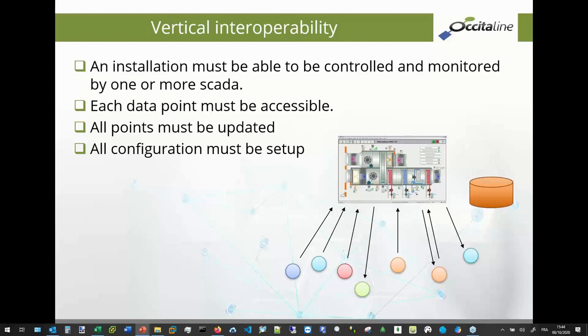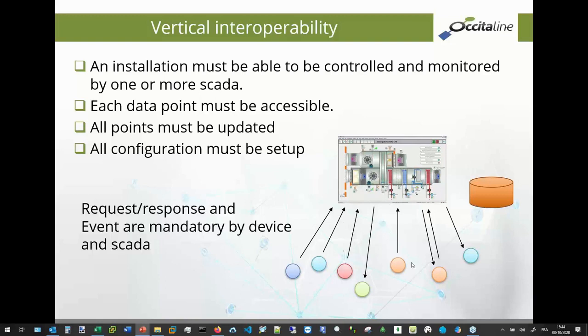I have two visions for interoperability. The first is vertical interoperability. This is when you have a SCADA with a database just behind it, holding the description of each data point on the field. Each device needs to receive or send information from or to the SCADA. This is a vertical communication, interoperability, with the same things.